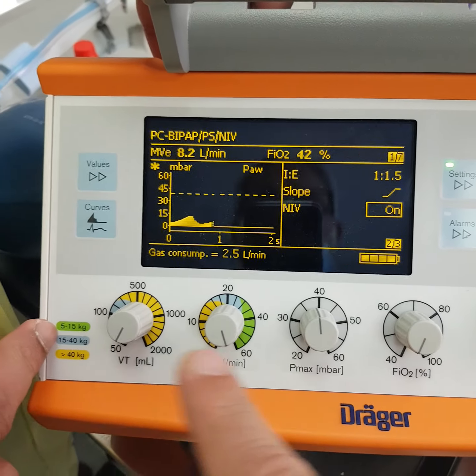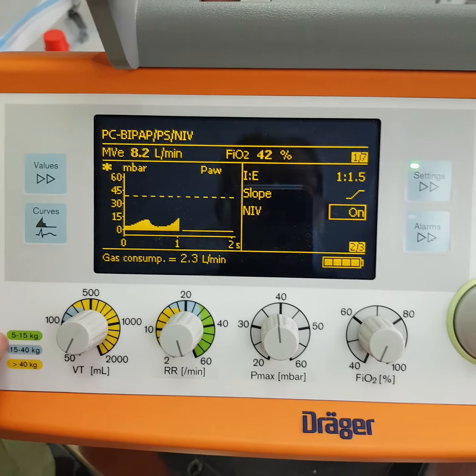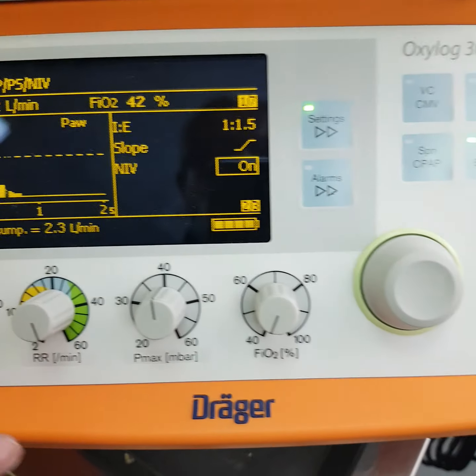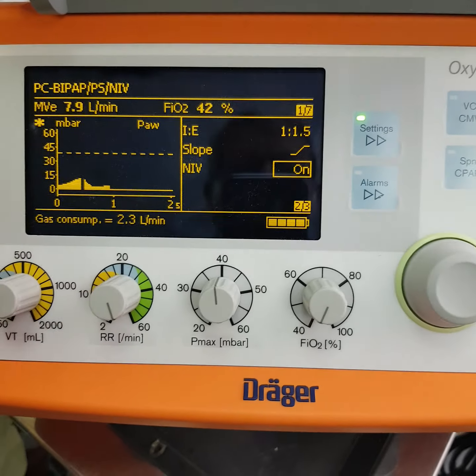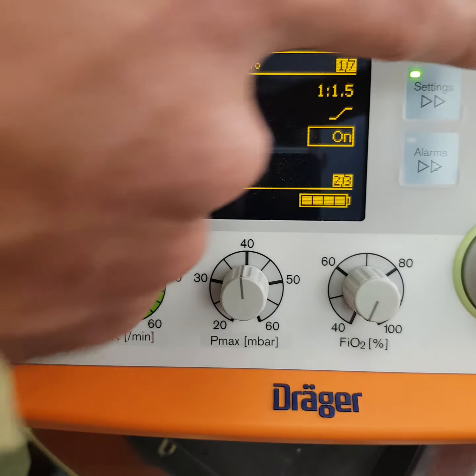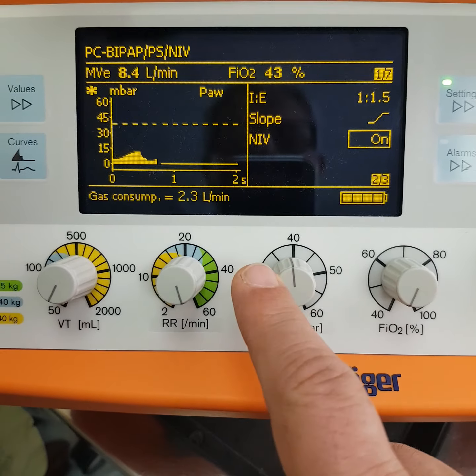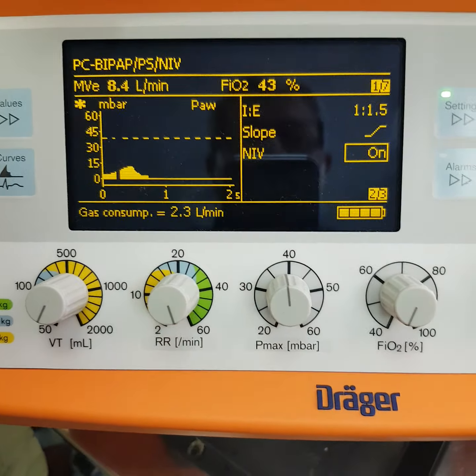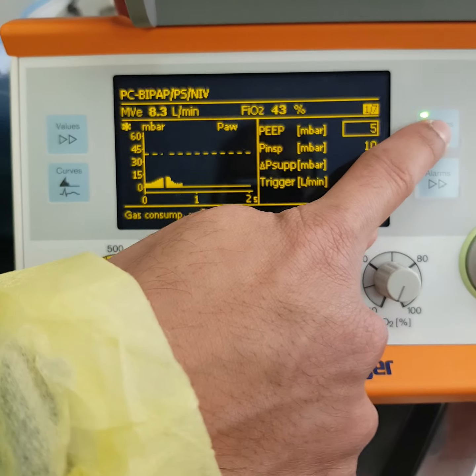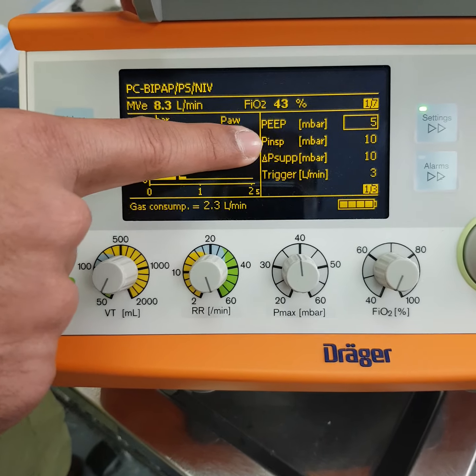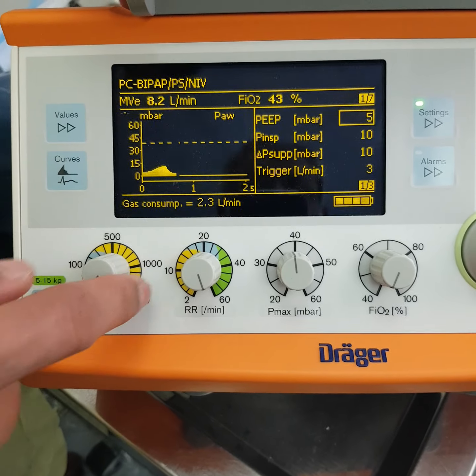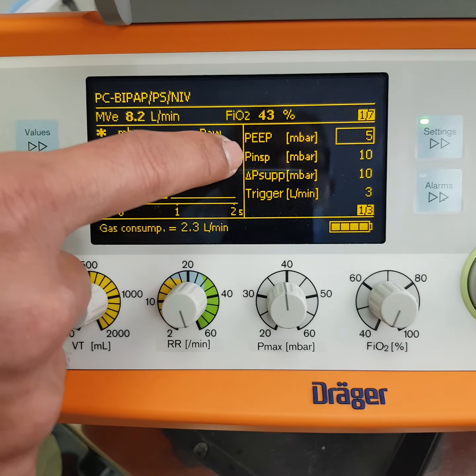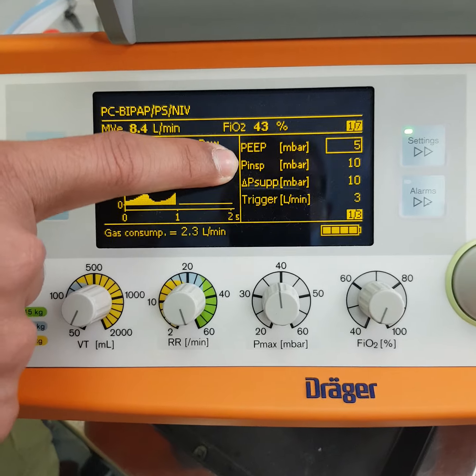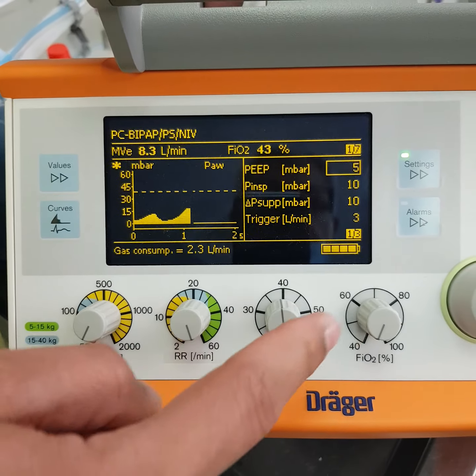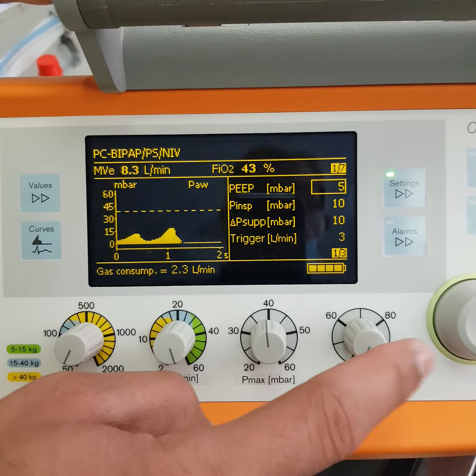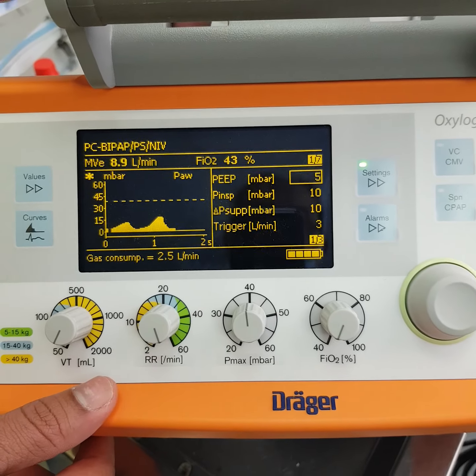Which knob of these four will be activated in case of non-invasive? So for PC BiPAP, similar to invasive, only the tidal volume will be deactivated, because you are on pressure control ventilation. So these three knobs are activated. Yeah. Okay. Since you have the inspiratory pressure, which is inside the screen, only the tidal volume will not be active, which will depend on the inspiratory pressure that you are going to set. Other than that, respiratory rate will be active, pressure maximum will be active, and FiO2 also will be active.